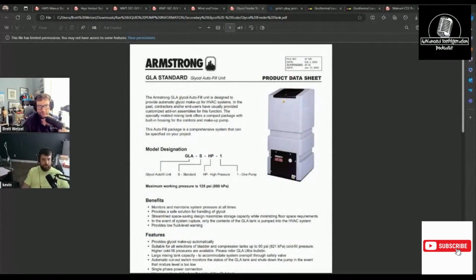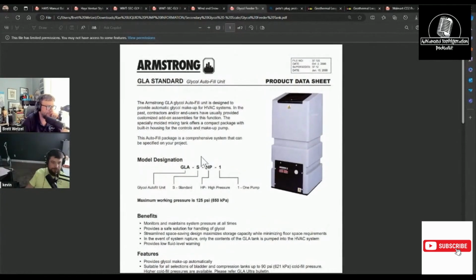But no, the feeder, I see its point. It's nice if you're on a roof and you don't have to force the glycol in. I will say this though, the glycol gets all gooey and nasty in that feeder tank. Oh, really? Yeah. Especially if it's open and it becomes a Band-Aid. It's like having a 100-pound cylinder hooked up to the system. Here's your feeder tank that you're talking about. Yeah, so the one we put in was way bigger. Yeah, this isn't that huge.